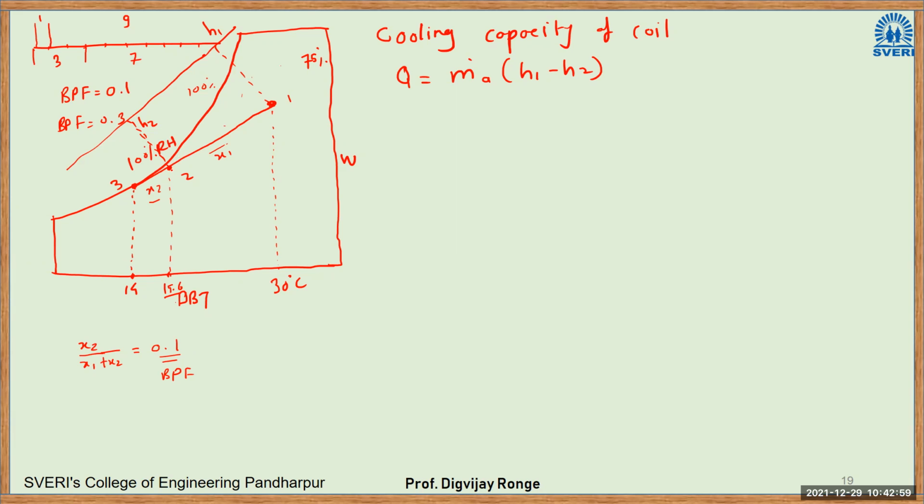Next thing here is the calculation of sensible heat factor. So I have to draw a triangle. If you remember from the last lecture, this will be a triangle. Here in this case, this will be the latent heat removed and this will be the sensible heat removed, right? And sensible heat divided by total heat will be our sensible heat factor. Okay, so now I will switch to the psychrometric chart. There we can get the values.